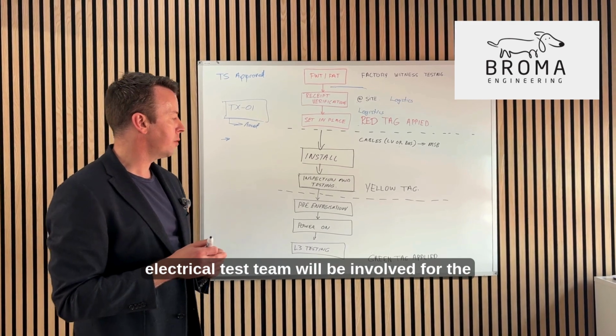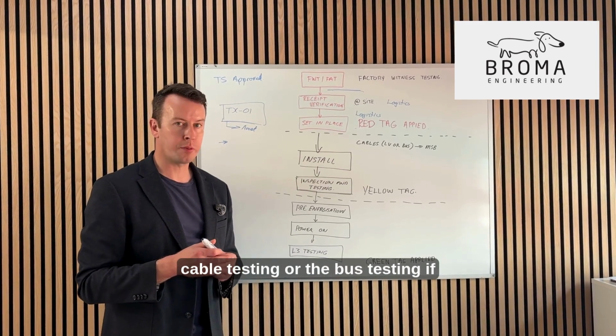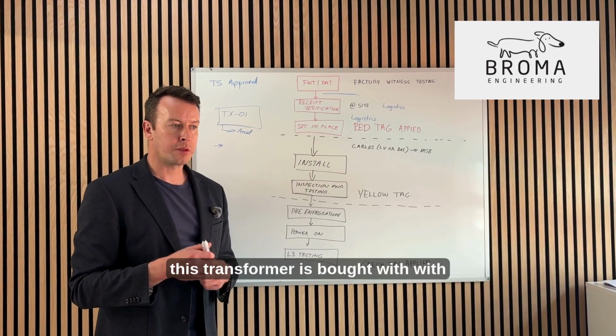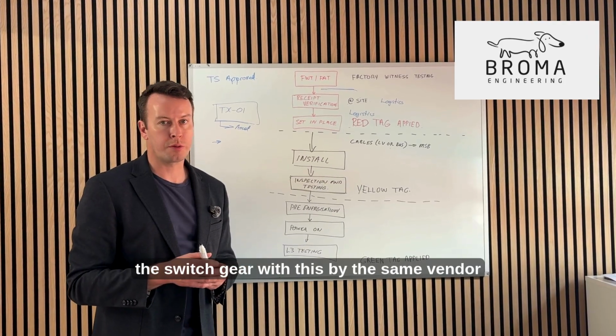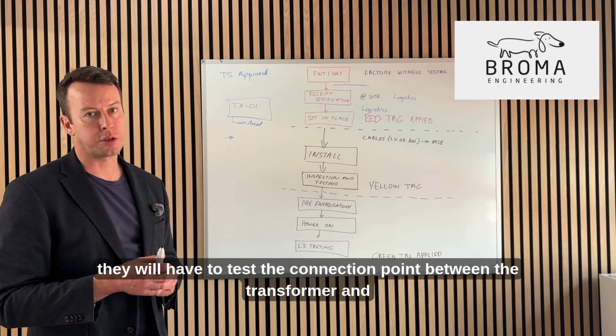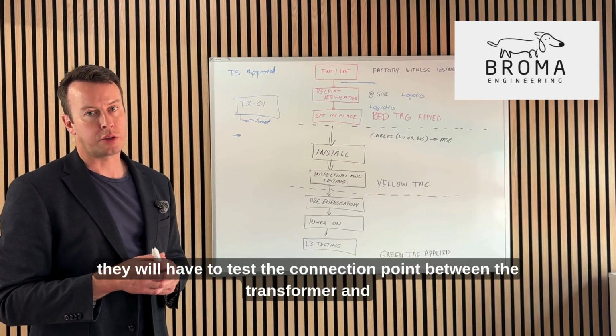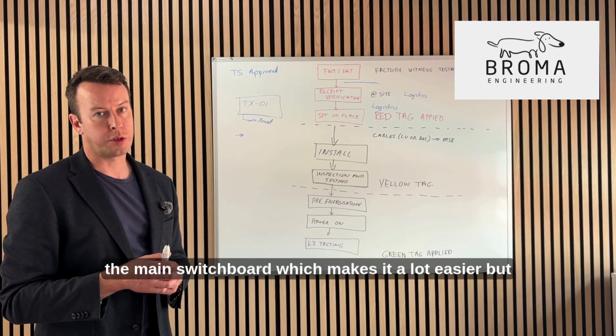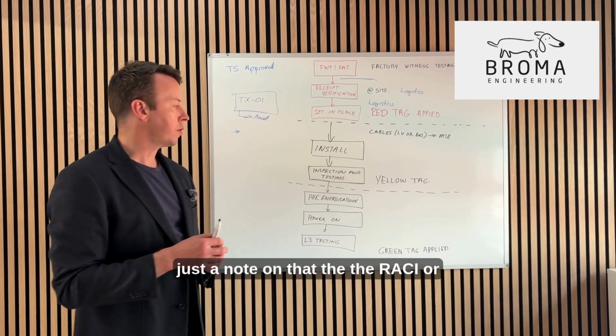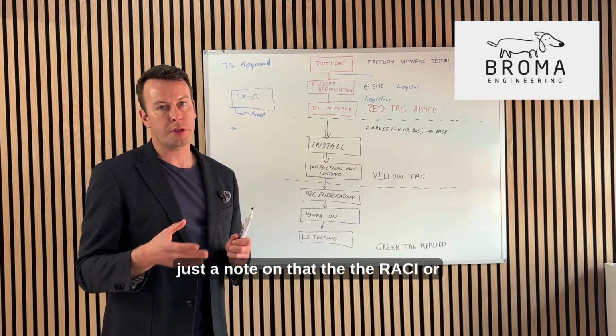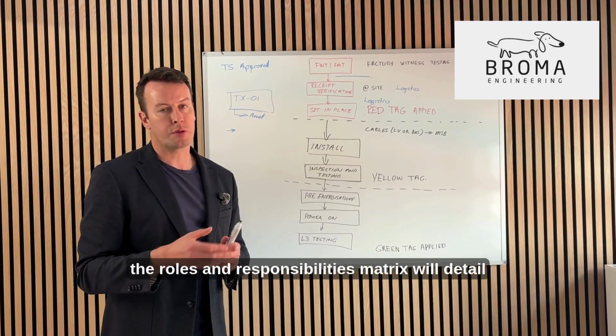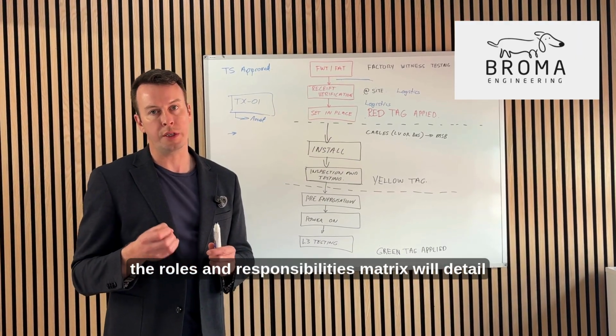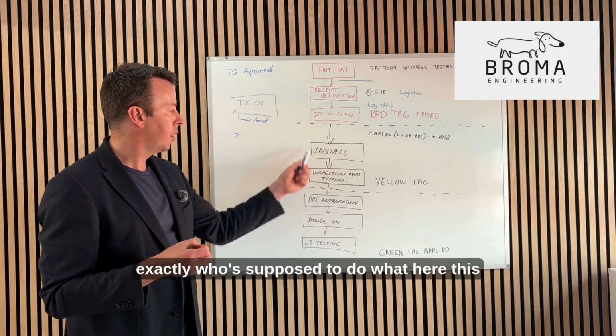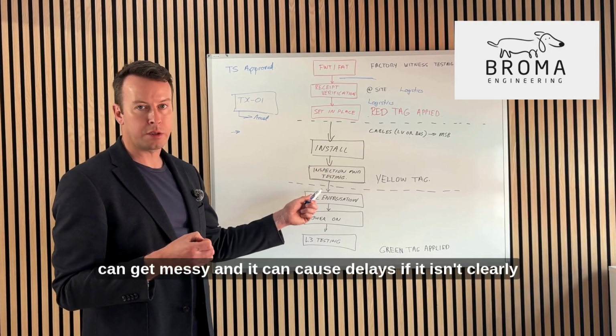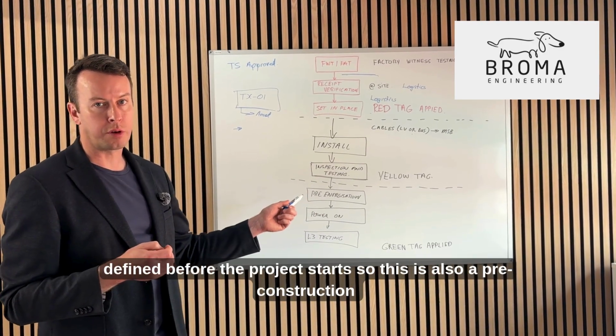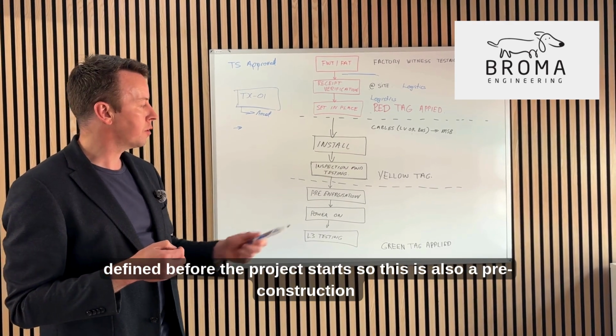The electrical test team will be involved for the cable testing or the bus testing. If this transformer is bought with the switchgear by the same vendor, they will have to test the connection point between the transformer and the main switchboard, which makes it a lot easier. But just a note on that, the RACI, or the roles and responsibility matrix, will detail exactly who's supposed to do what here. This can get messy and it can cause delays if it isn't clearly defined before the project starts. So this is also a pre-construction.